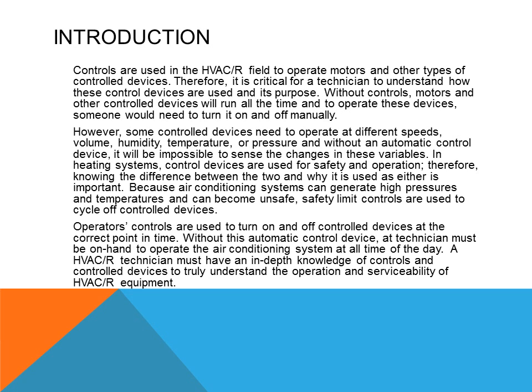In air conditioning systems, control devices are used for safety and operation. Knowing the difference between the two is important. Because air conditioning systems can generate high pressures and temperatures and can become unsafe, safety limits are used to cycle off the control device. Operator controls are used to turn on and off control devices at the correct point in time. Without automatic control, a technician must be on hand to operate the system at all times.